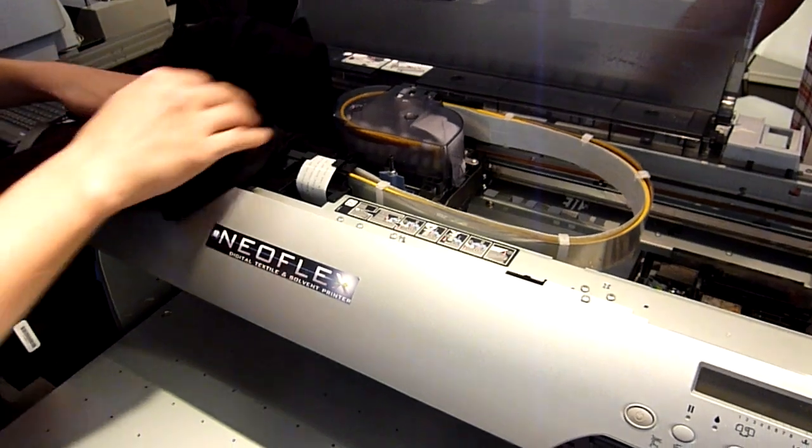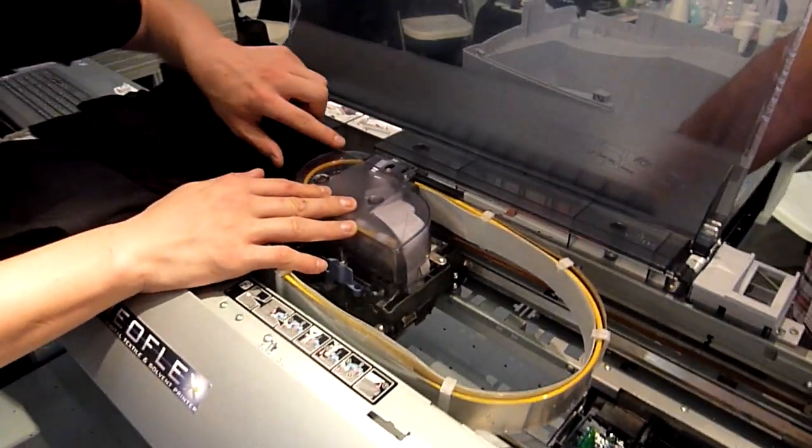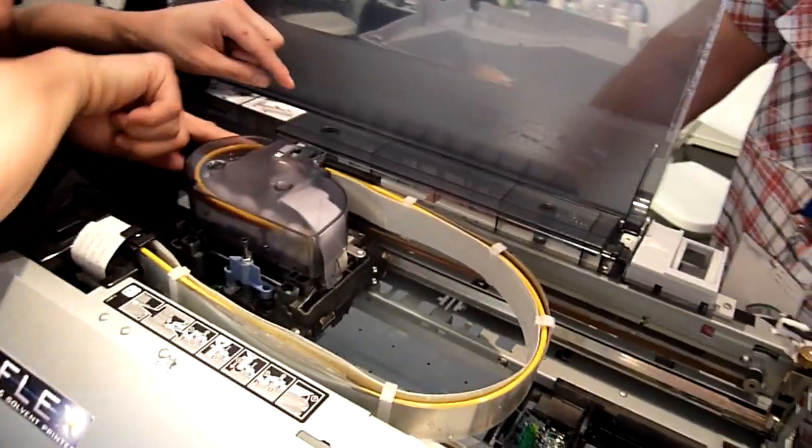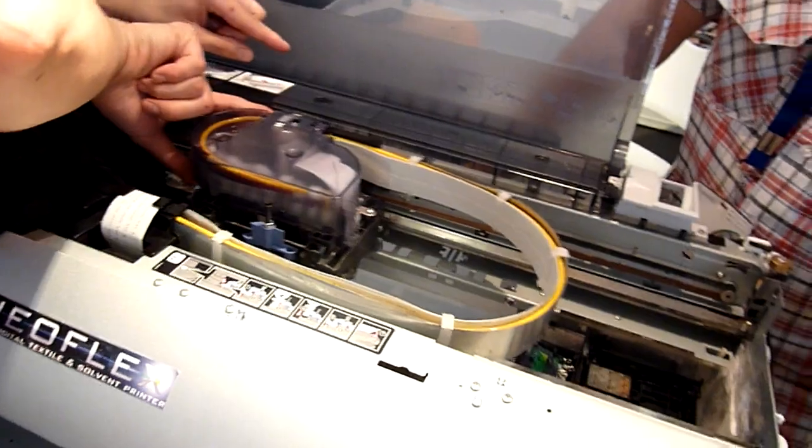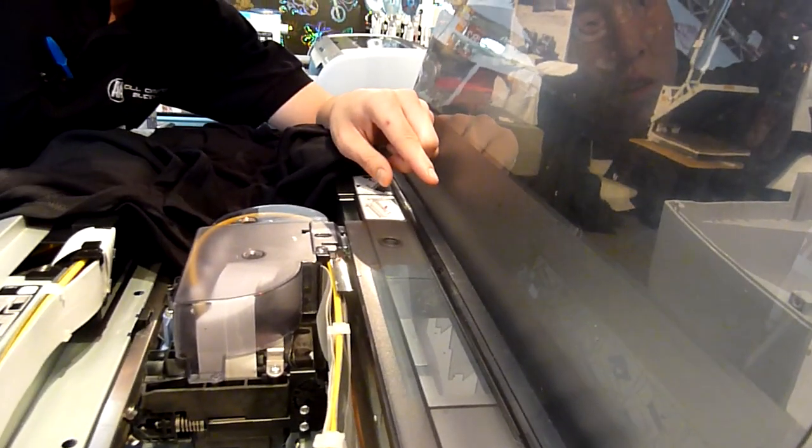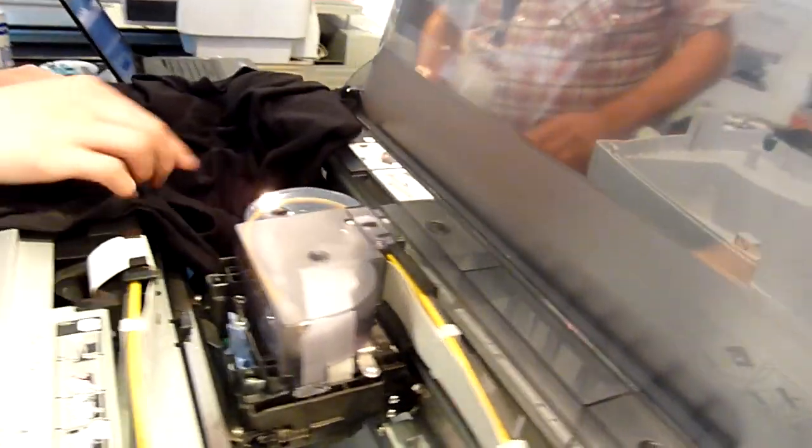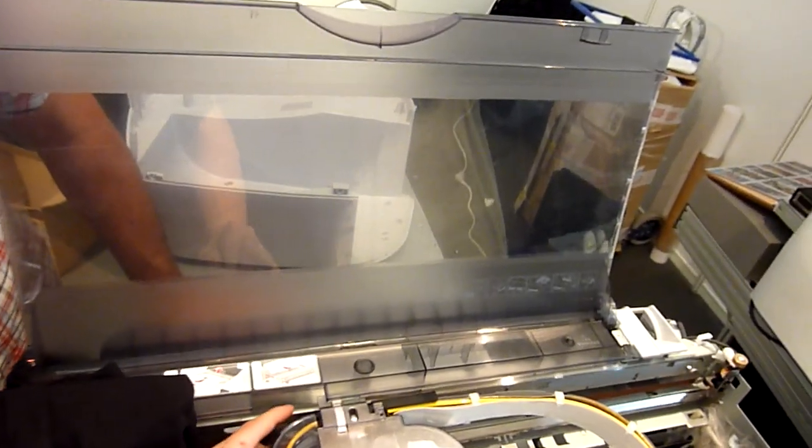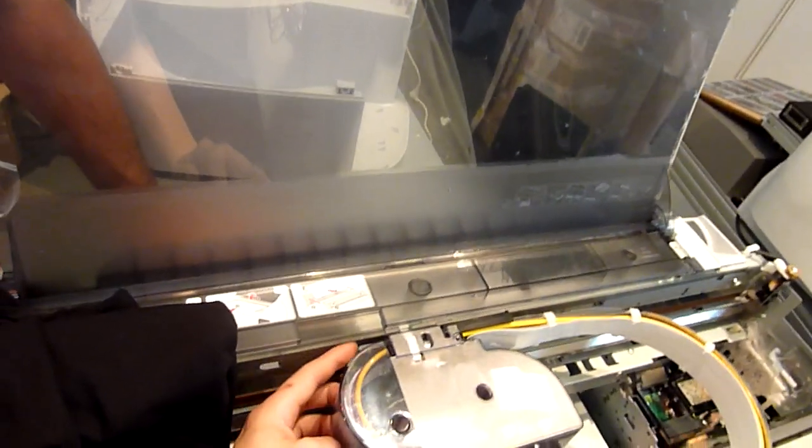Now, first thing you do is there's an encoder strip that Justin was talking about. It's in between these grooves right here. It's in between, like a groove. Now, what you're going to do is you're going to pull it down, twist, and pull up. So it's out. There you go. Now it's out of the groove.